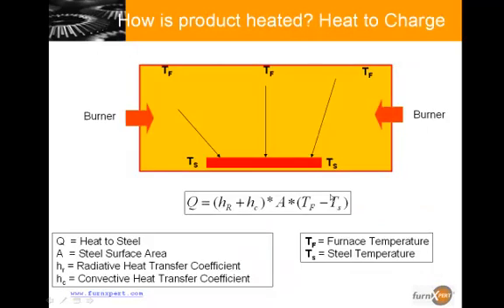The steel is heated by high temperature zone walls. The zone walls attain high temperatures from the flames of the burners. The equation of heat flow is shown above where q is the heat to the steel, A is the charge surface area, Tf is the zone wall temperature as read by the thermocouple, and Ts is the temperature of the steel at any instant.